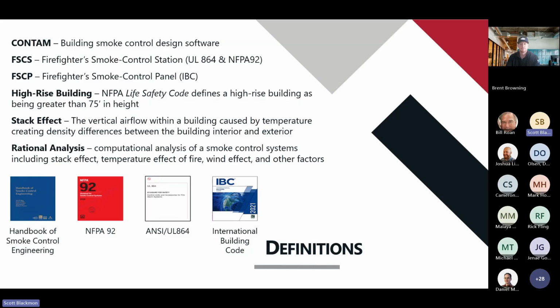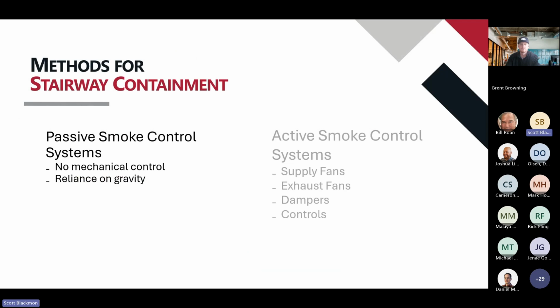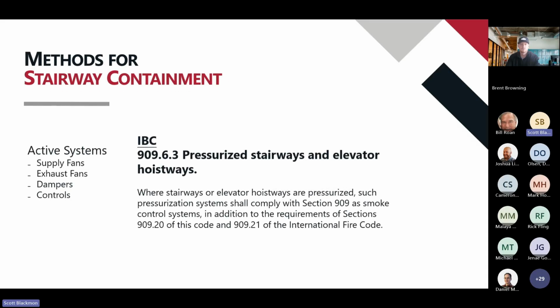And then stack effect, that's going to be that natural flow of air through the building. And then rational analysis, that's going to be that computational analysis to show how smoke flows through the building. So when we talk about methods for stairwell containment, there's two different types. We've got a passive smoke control system. That's going to be what you see in your Holiday Inn Express, one of those smaller hotels, a 3-4 story building where they've just got doors to the stairwell that close, to keep smoke out. It's one of those best of luck type situations. Then active systems is really where we come in, and that's where you're using supply or exhaust fans, dampers and controls to really control and mitigate the pressure inside those stairwells or hoistways.